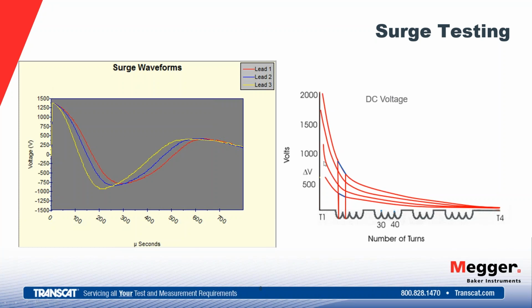As we apply more and more voltage, this impulse nature of the energy that we're applying to the motor causes this nonlinear drop across the winding. So here we have our T1 connection to our T4. These represent our turns at the bottom. And as we raise that voltage up, we're getting a differential between turns. These blue lines here help guide our eyes as to how much drop there is between turns as we raise voltage up.